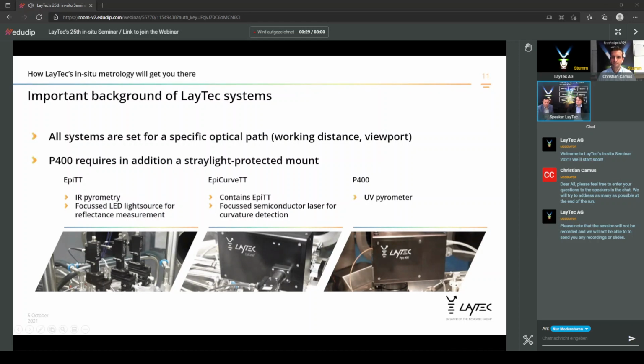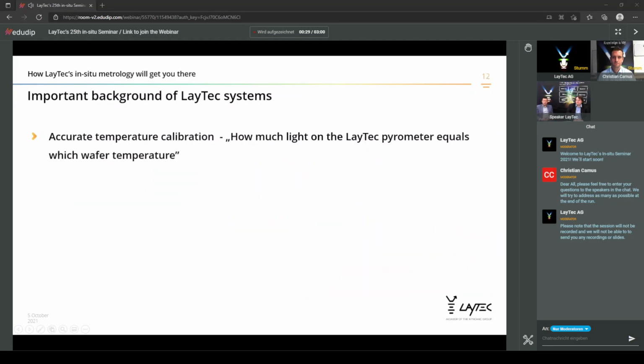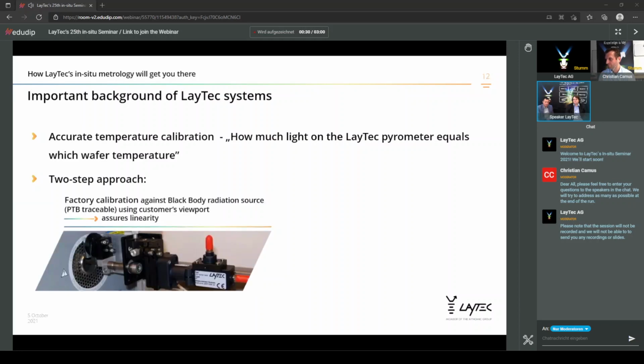We mentioned that the most important parameter is the temperature, so to measure the temperature value very accurately. The temperature measurement in case of pyrometry means how much light on the LayTec pyrometer equals which true wafer temperature. LayTec systems are set with a two-step approach. So we start in the factory when the system is assembled with a black body calibration, which is traceable to the Physikalisch-Technische Bundesanstalt, so the German National Standard Organization, so that this black body temperature is according to a real standard and showing the absolute value.